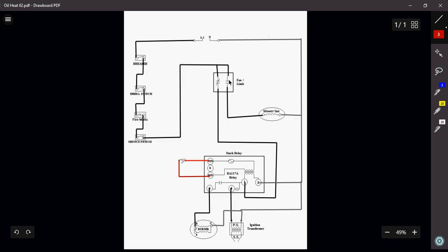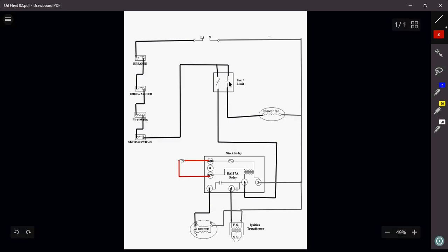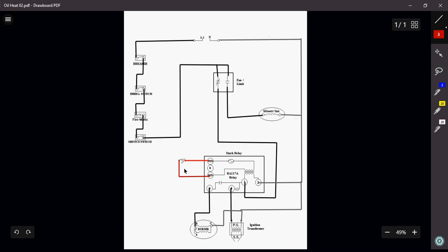Once that happens, my 140, my normally open contact, because now the furnace is going to be all nice and warm, about 140, maybe 150 degrees. Once that happens, that switch actually closes, which will bring on my fan, which will now begin to heat up the space. And that will continue to operate until the thermostat is satisfied.